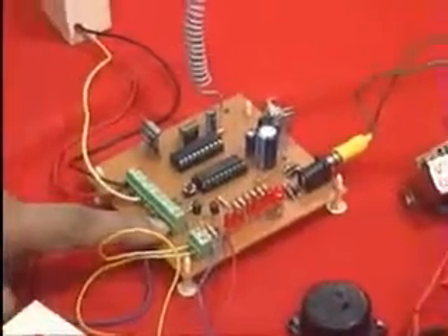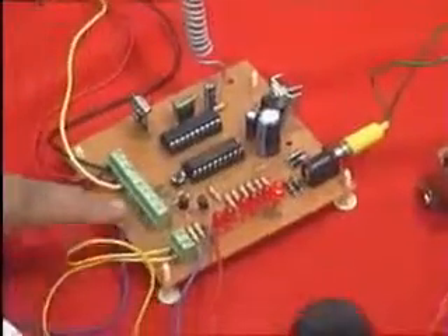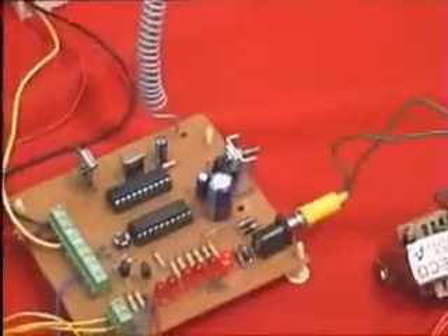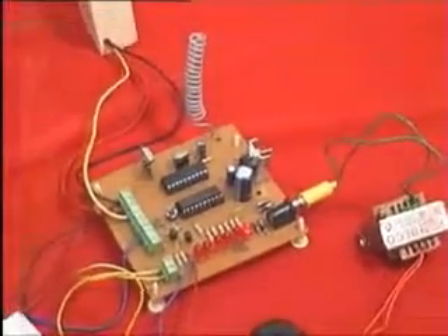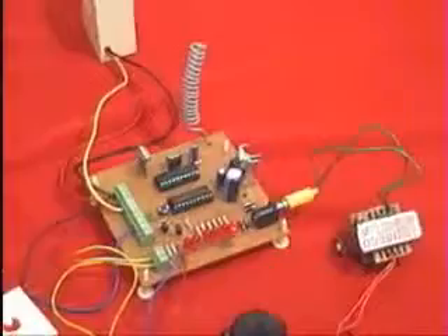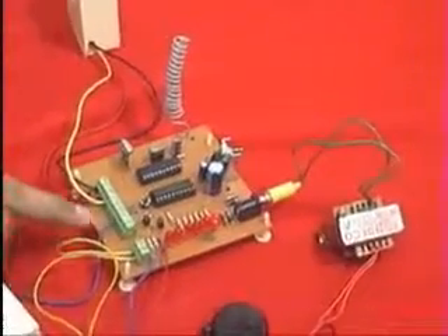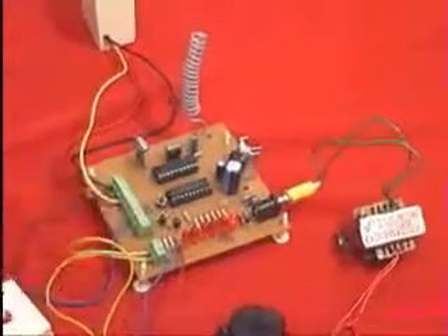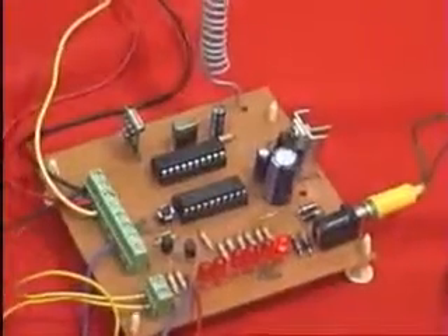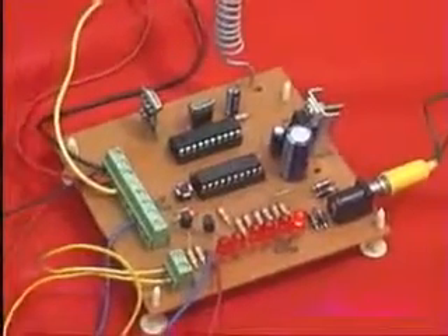Normally the gas sensor has a normally-open contact relay. So the output of this normally-open contact relay has to be connected to those two terminals. Whenever gas is detected, the relay comes on and makes contact, which I am now simulating by making contact with this piece of wire.